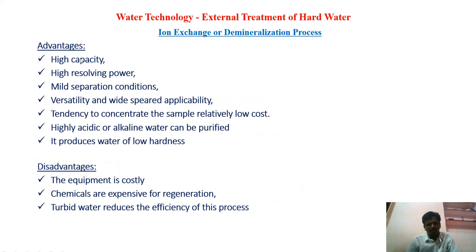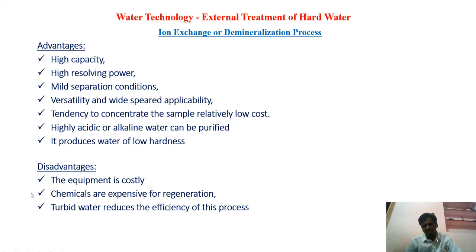The advantages are: it has high capacity to remove both cations and anions, high resolving power, and separation conditions are very mild. It can be used to treat both acidic and alkaline water, and the water coming out has very low or no hardness. The disadvantages are: the equipment is very costly, and the chemicals used to regenerate saturated resins are expensive. If the water is turbid, it may reduce the efficiency of this process, as turbidity can clog the functional groups.